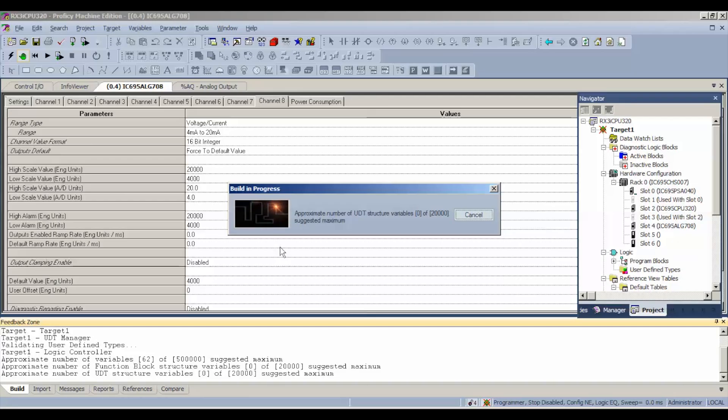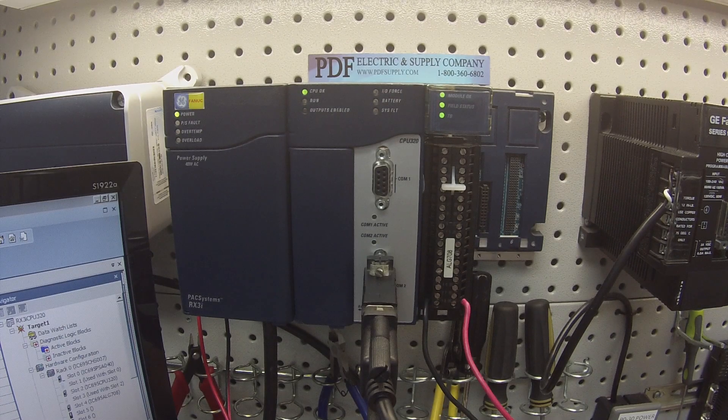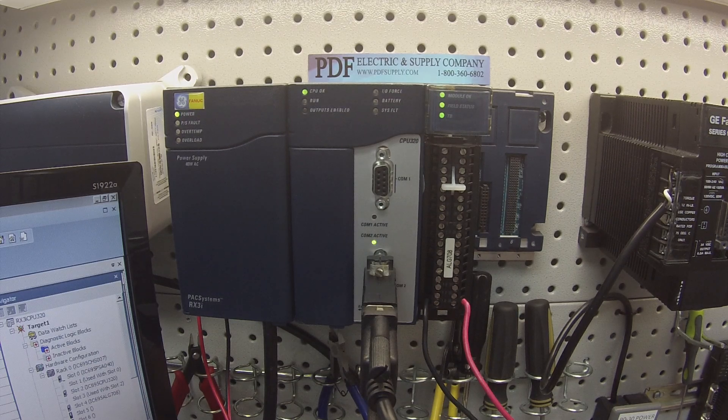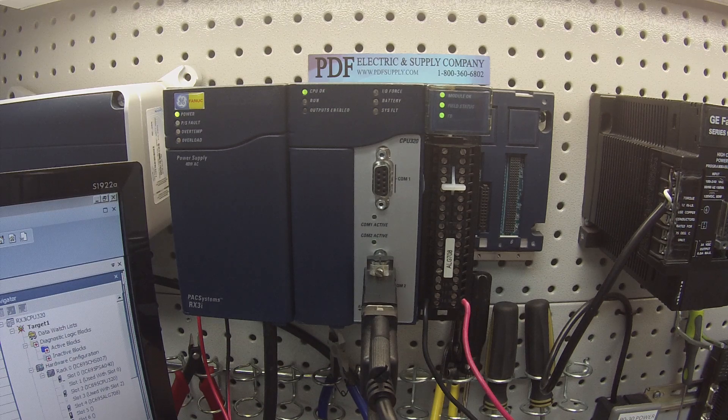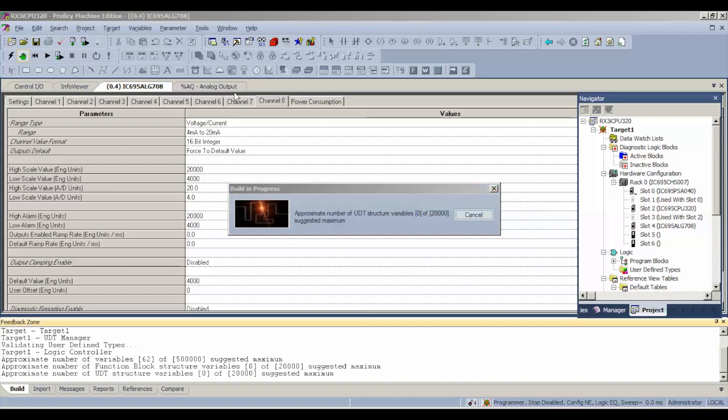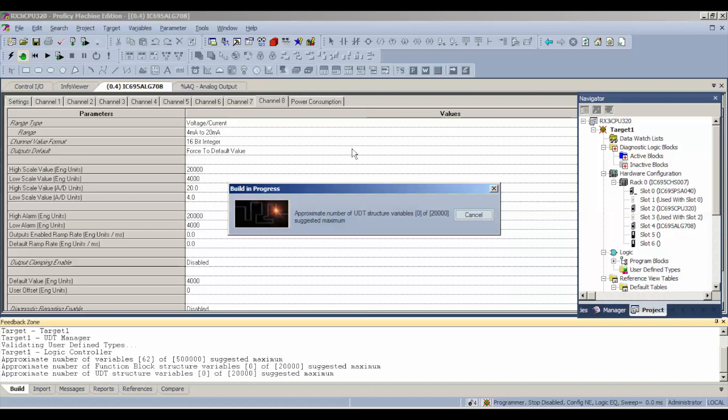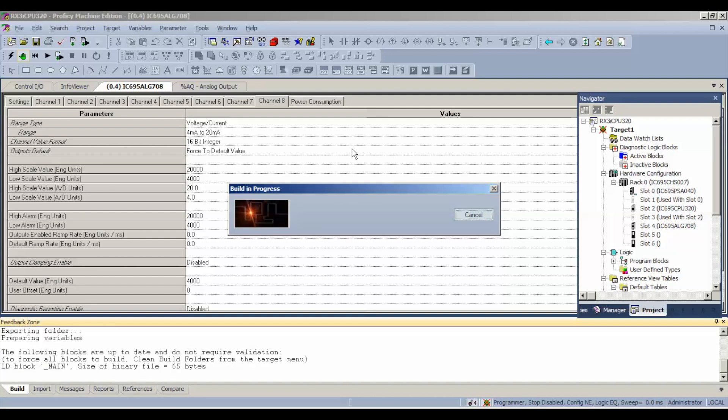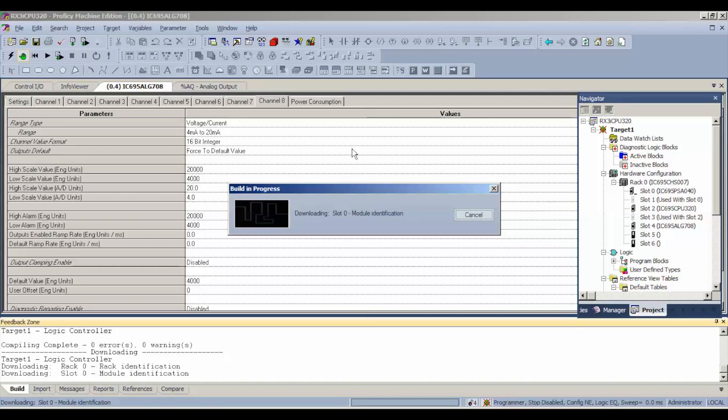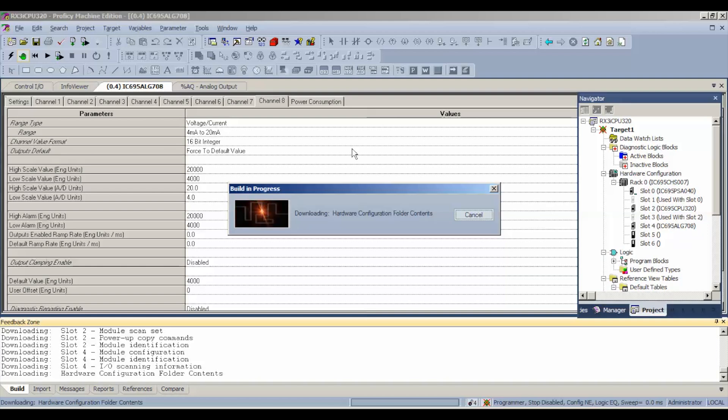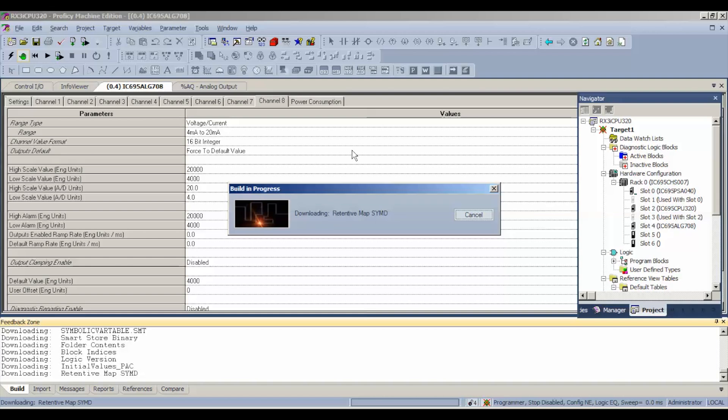Next thing that you want to do while you're waiting for it to download is switch your multimeter over to read milliamps and make sure it's milliamps in DC, not AC, otherwise you're not going to get a reading. I don't want you to think that there's something wrong with the device if there really isn't. Once the download is complete, it'll allow us to turn the outputs back on and be back in run mode. I think we're just about there. Apparently, there's a lot of information to download with this particular device.